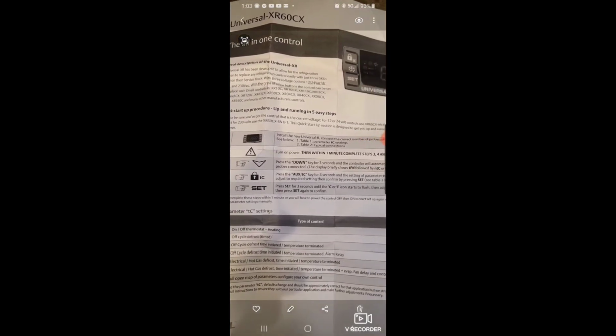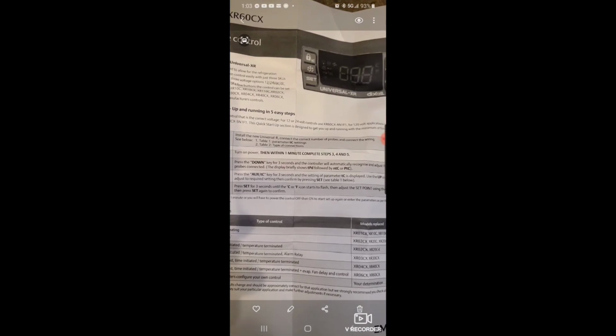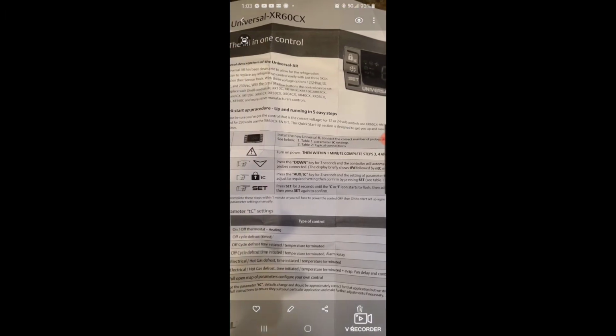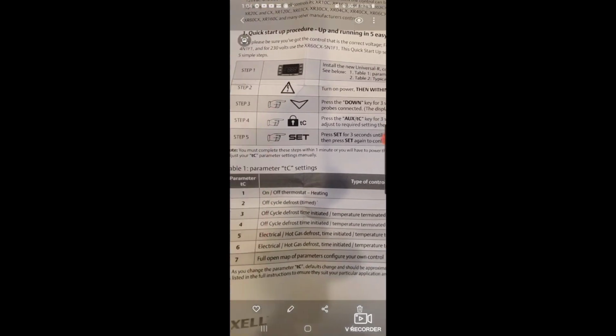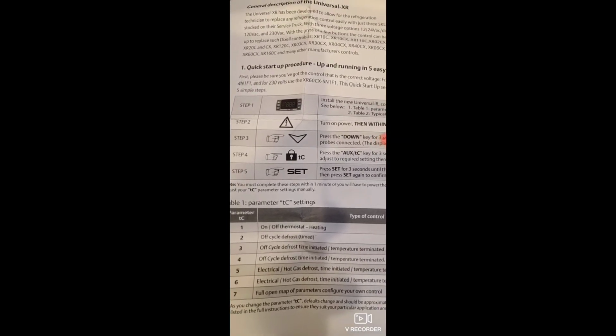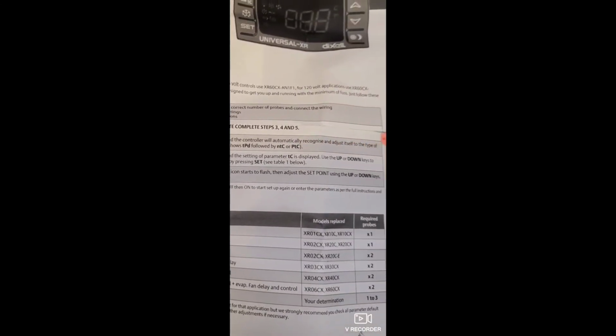So I'm going to do that, then press auxiliary TC for 3 seconds. Use up and down keys to adjust the required settings and confirm. So that's for the parameter, which is this table down here below. For the off cycle, see, this is just off cycle defrost, so I'm gonna go with 4. Defrost time initiated, temperature terminated, alarm relay. So I'm gonna go with number 4 on there. And then it says step 5, press and hold set for 3 seconds, Celsius or Fahrenheit, and then adjust the set point.